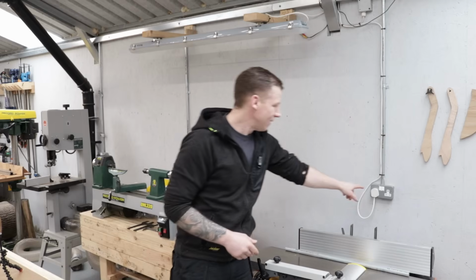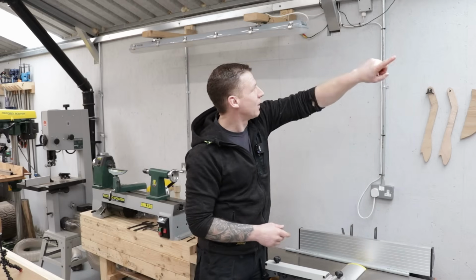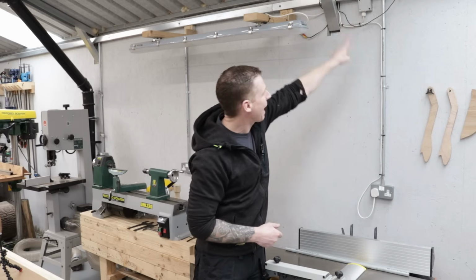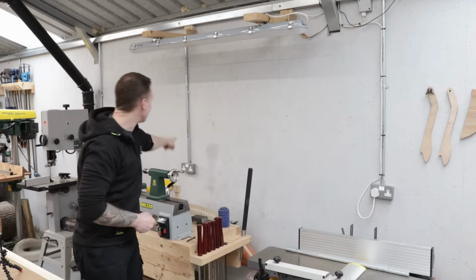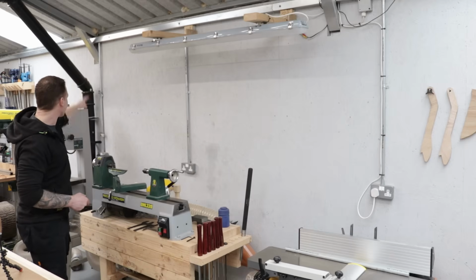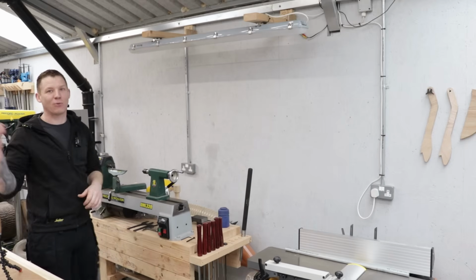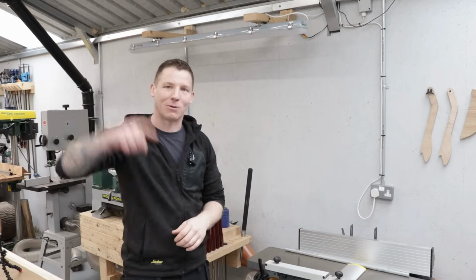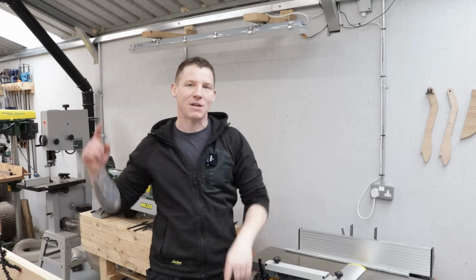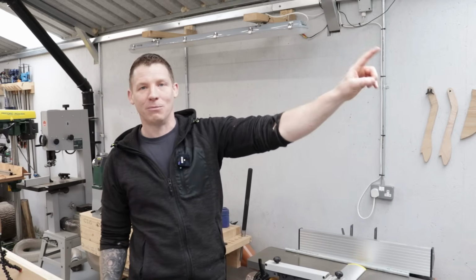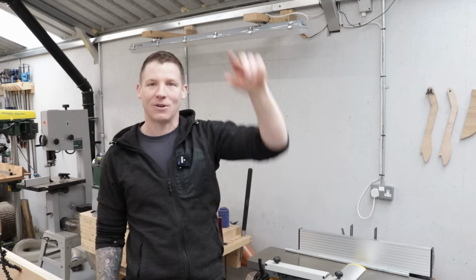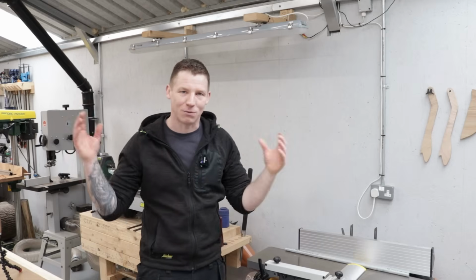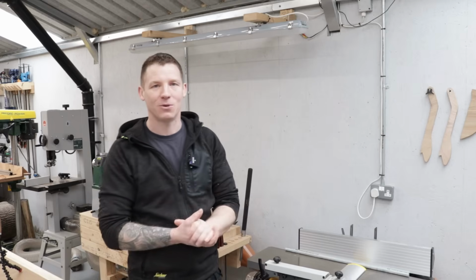So if you think about it, here's my first socket on this circuit. So it's out from my board, down here, back up, across to here, down here, back up. So I'm adding meters all the time. And if I get around my workshop and I've gone up and down the walls, I've probably added 30 meters of cable to my mains cable back to my house and out. So it gets way too long, the loop impedance will be too high, and that gets dangerous, and I'll show you why in a minute.